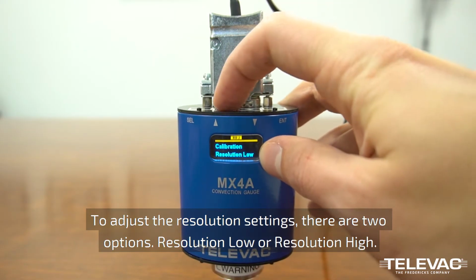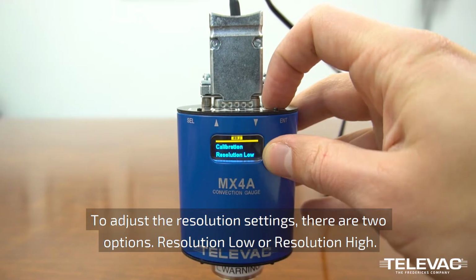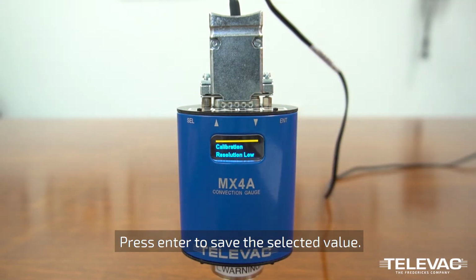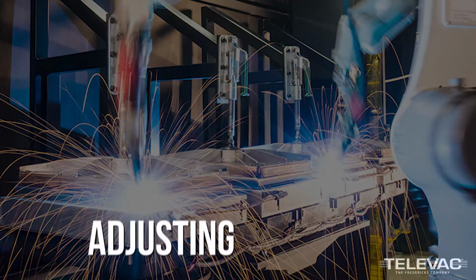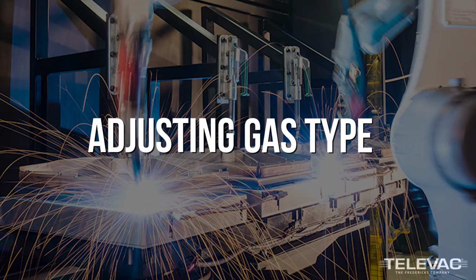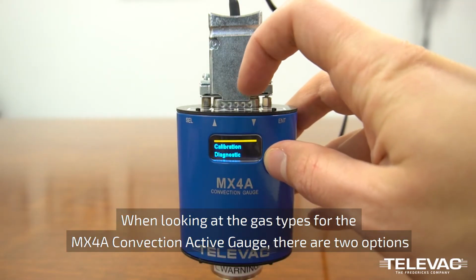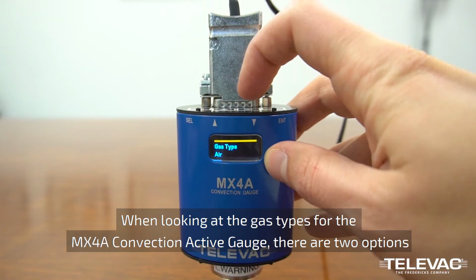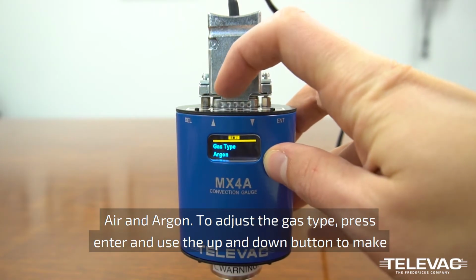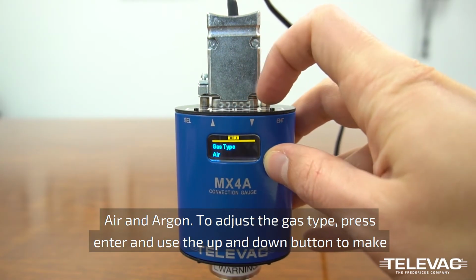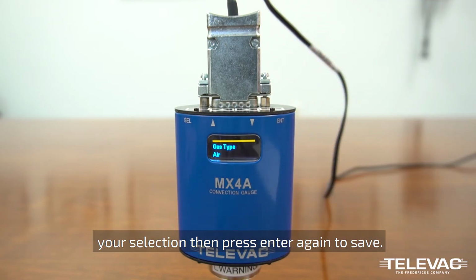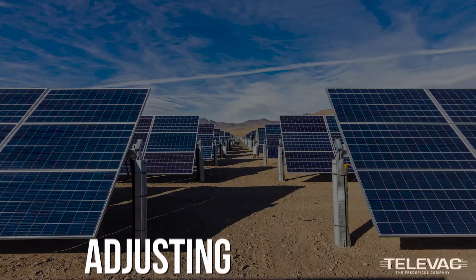To adjust the resolution settings, there are two options, resolution low or resolution high. Press enter to save the selected value. When looking at the gas types for the MX4A Convection Active Gauge, there are two options, air and argon. To adjust the gas type, press the enter button and use the up and down buttons to make your selection, then press enter again to save.